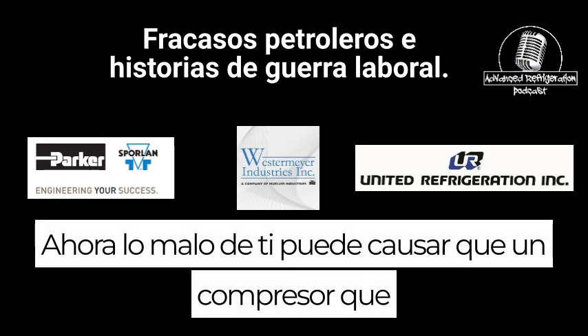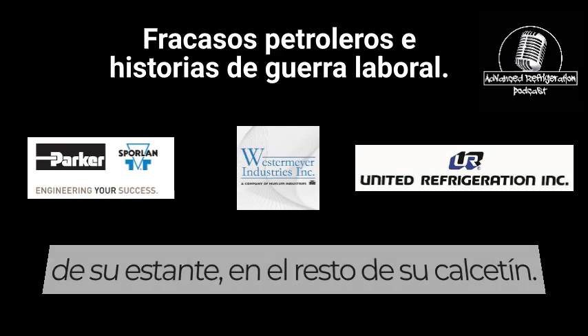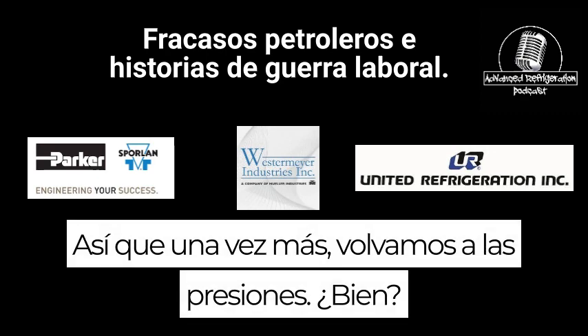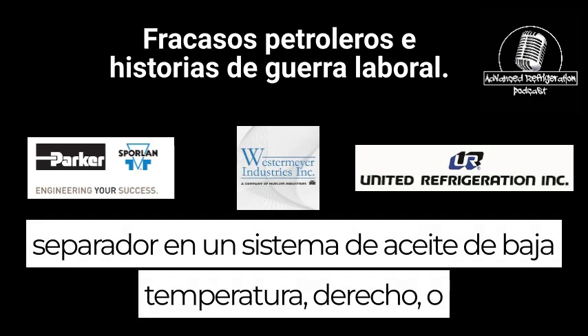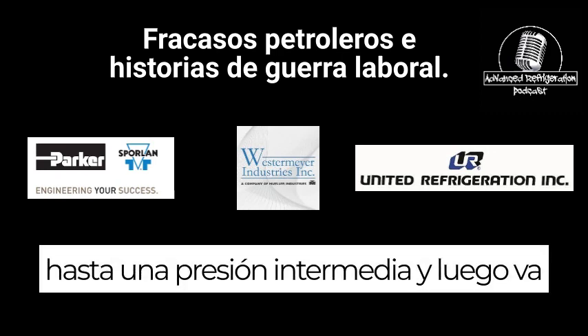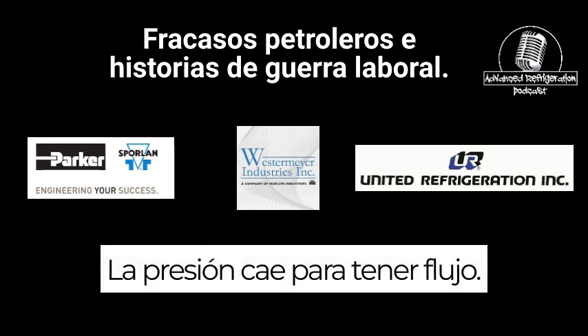Now the bad thing is that one compressor with piston or valve issues can cause oil failures on the rest of your rack, on the rest of your side. So once again, I'm going to go back to the pressures. I'm going to go over this again until I'm blue in the face. On a low temp oil system, we have discharge pressure at our oil separator, then it goes down to an intermediate pressure, and then down to the crankcase pressure. You need the pressure drops in order to have flow.